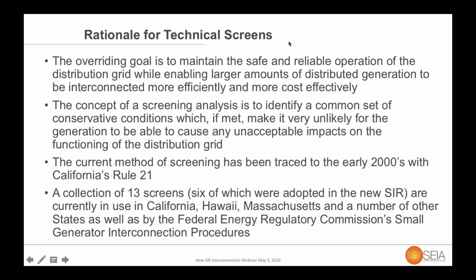Okay, great. So the overall rationale for the technical screens, as Melissa has mentioned, is that we have this overriding goal to maintain the safe and reliable functioning of the distribution system, while at the same time enabling systems that will not have impacts on safety or reliability to be interconnected more efficiently and more cost effectively.